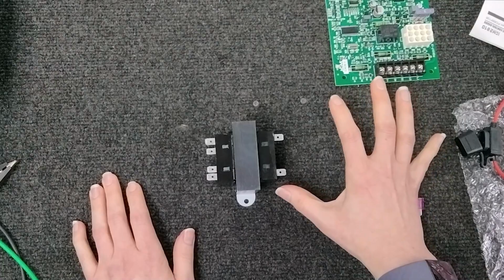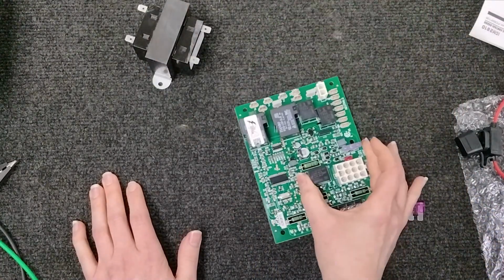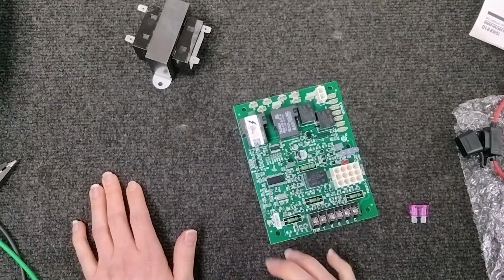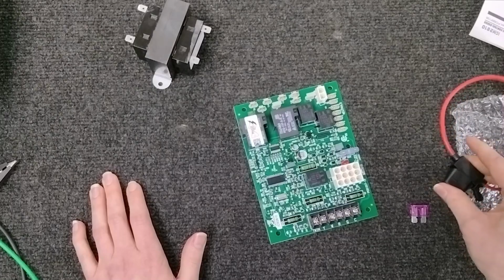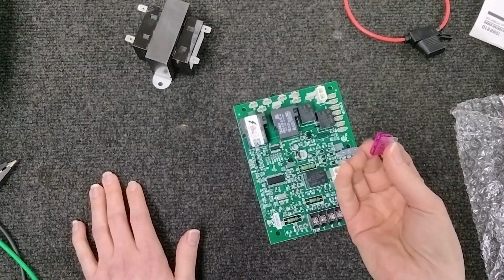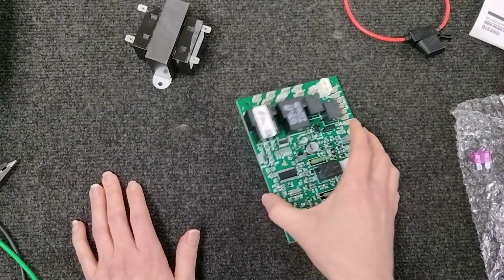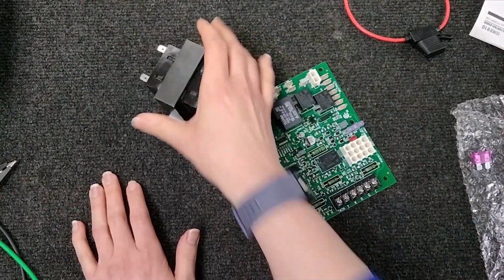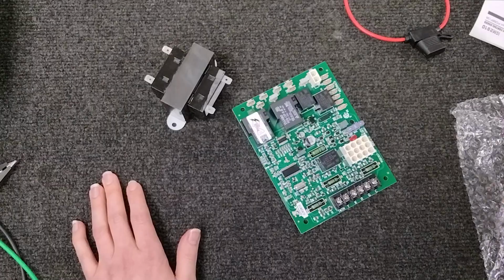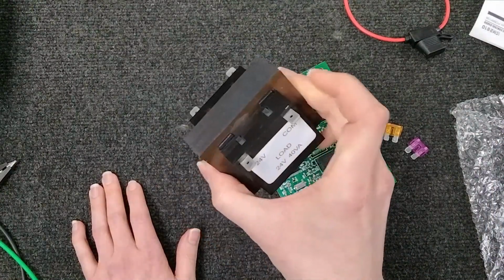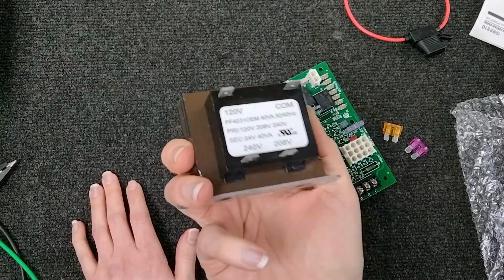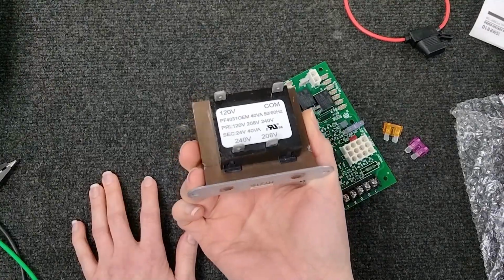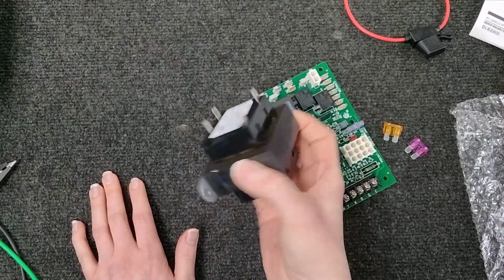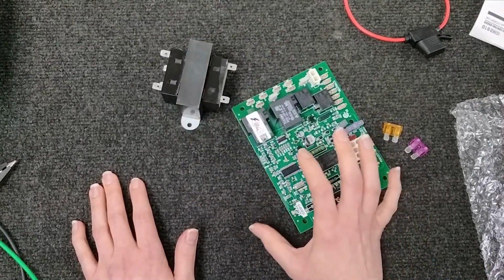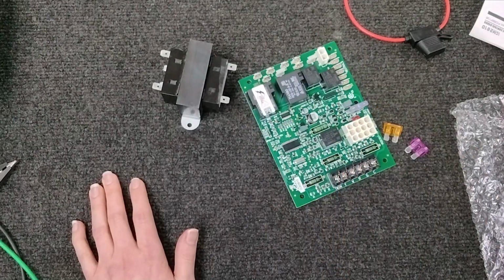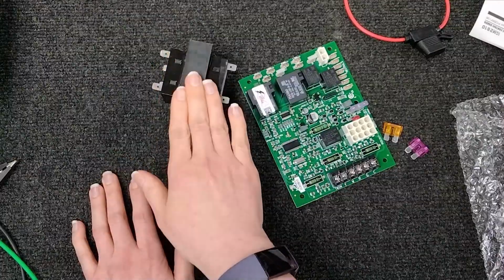So once we've ruled all of this out and we've caught, hopefully, what's been going on with our gas units, it's going to really help to know all of these things, so that you're not replacing your control board or your transformer. In a previous video, I spoke about knowing whether a transformer is good or bad, because if it's bad, nothing's going to come on, heat or cool, either one. If something comes on in your unit, you see a light on your control board, or your cooling comes on but not your heat, your transformer is doing its job and it is fine.